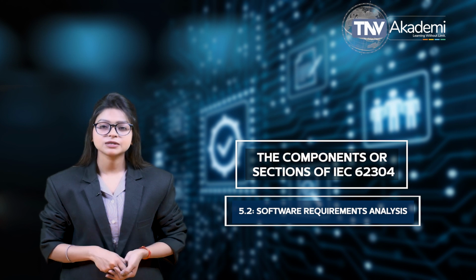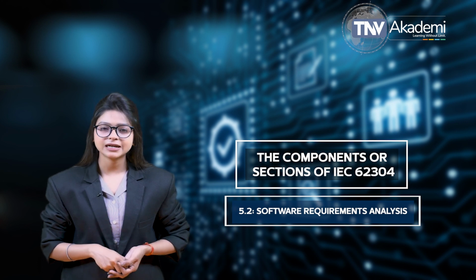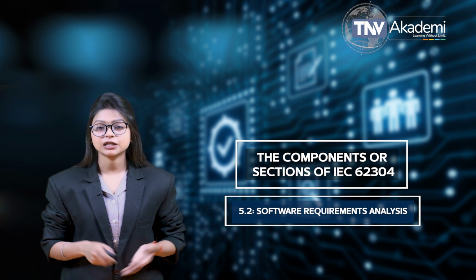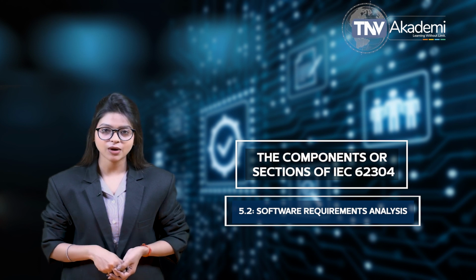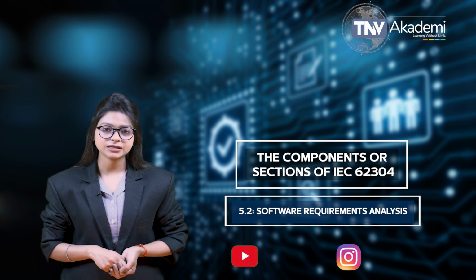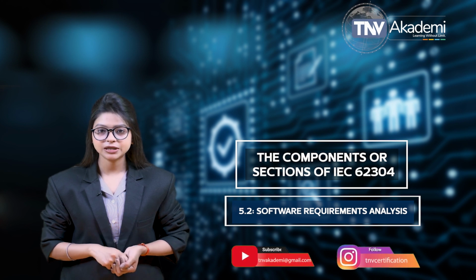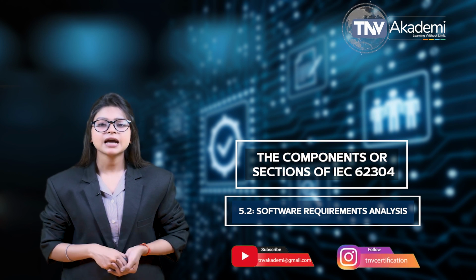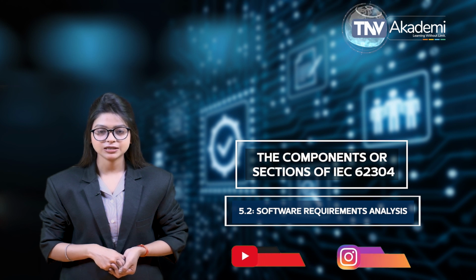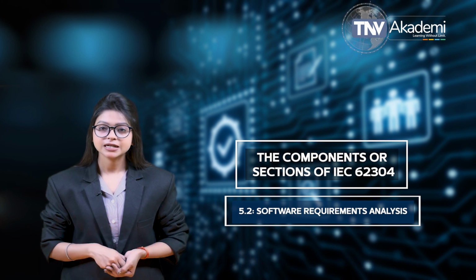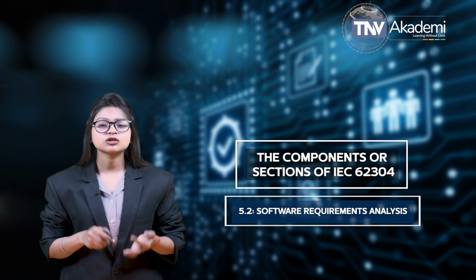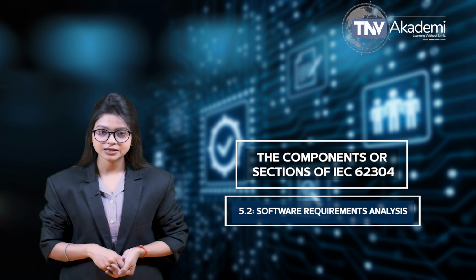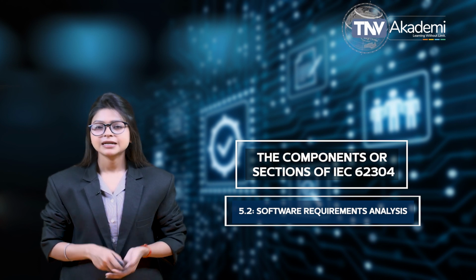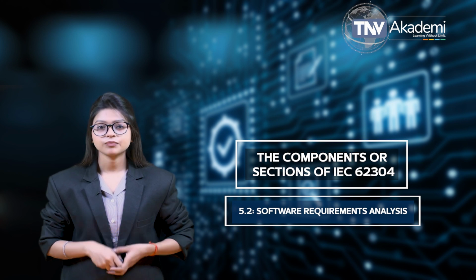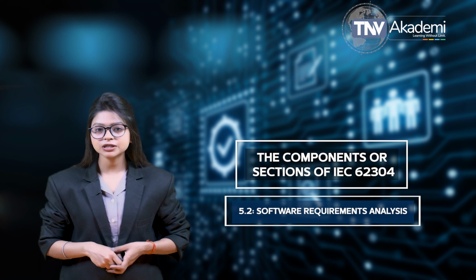5.2. Software requirements analysis. This subclause specifies how software requirements analysis is to be conducted, including specification of software requirements from system requirements, functionality and capability requirements, interface and compatibility specifications, cybersecurity requirements, data structures requirements, installation and maintenance requirements, verification requirements, testing and acceptability criteria requirements, and updates and regression testing requirements.